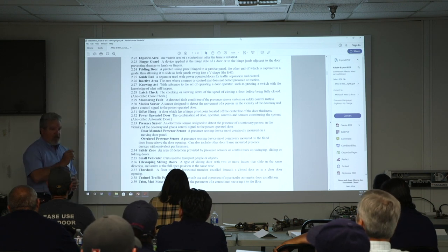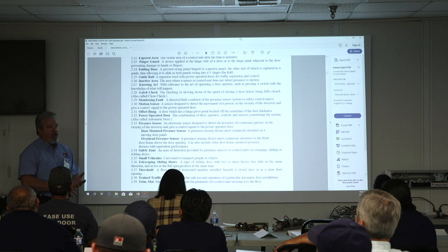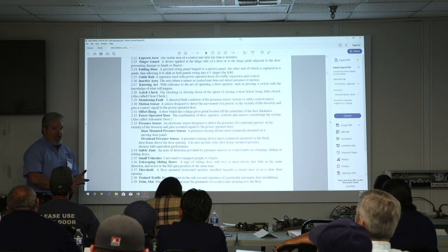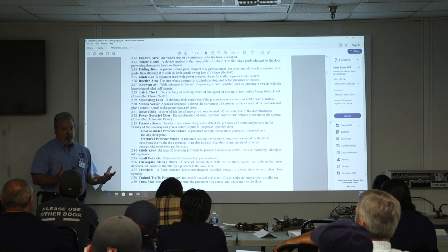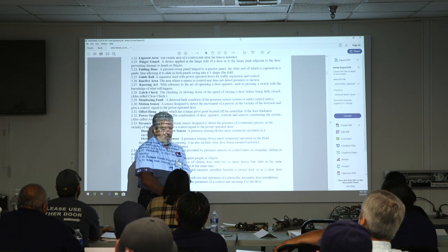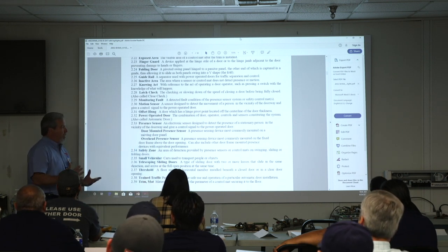Most presence sensors have a selectable period of time on them, ranging from 2 seconds up to, let's say, 180 seconds. Somewhere in that range, they're selectable, with two or three choices of time. So if you have it set for a 2-second relearn time, and I move into a presence sensor zone and remain perfectly motionless, which is pretty hard to do, after 2 seconds it's going to relearn me being in its zone, and it's no longer going to signal. We'll talk about more of that in a minute.